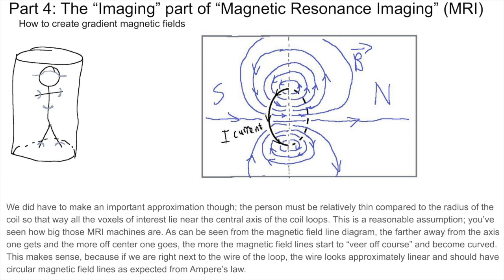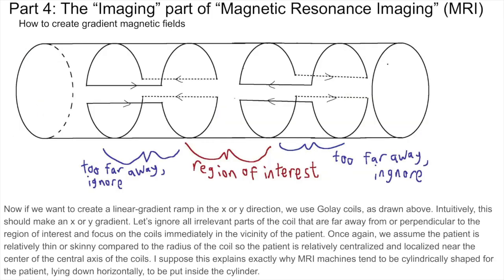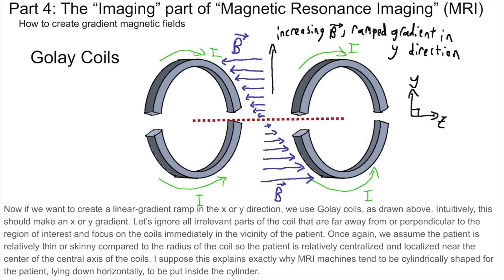You've seen how big those MRI machines are. As can be seen from the magnetic field line diagram, the farther away from the axis one gets and the more off-center one goes, the more the magnetic field lines start to veer off course and become curved. This makes sense because if we are right next to the wire of the loop, the wire looks approximately linear locally and we should have circular magnetic field lines as expected from Ampere's law. Now, if we want to create a linear gradient ramp in the X or Y direction, we use Golay coils as drawn above. Intuitively, this should make an X or Y gradient. Let's ignore all irrelevant parts of the coil far from the region of interest and focus on the coils immediately in the vicinity of the patient. We assume the patient is relatively thin compared to the radius of the coil so the patient is relatively localized near the central axis of the coils.